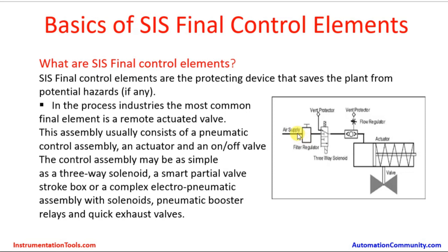The air supply comes into a filter regulator which absorbs moisture, then passes through a three-way solenoid valve. The solenoid either passes instrument air to the actuator body, where air works against the spring pressure to push it down and open the valve, or in an emergency situation the solenoid shifts so that the air is vented out through the vent port. The spring then acts with its force to close the valve. This is a typical on-off assembly and its components.